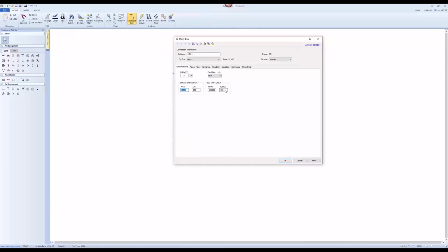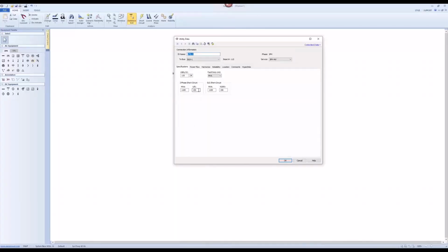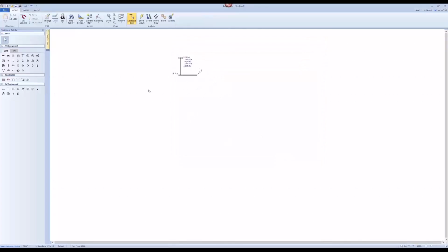utility strength, right? For three phase, I would assume that the zero sequence is the same, that you have similar three-phase short circuit level and single line to ground short circuit level, right? So that's what I use as my input. Now going downwards, oh, by the way, I did not put too much value on the X/R ratio. Maybe 40 is a typical number we use as well, right? So we put a 40 as well.